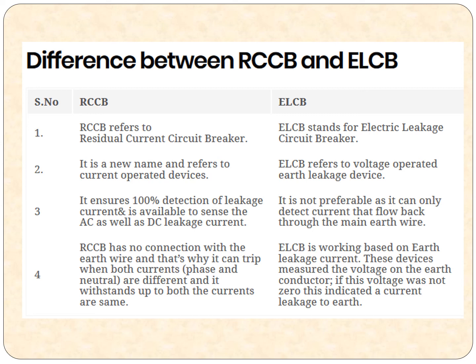That means you are supplying some current, it is energizing the load, and it comes back through the neutral. So the phase current has to be equal to the neutral current. But if you are having a shock, or an overload happens, your phase current and the return current will not be equal. It will be somewhat higher. That is the way it detects and makes protective action, which is 100% efficient. So ELCB works based on the earth leakage. These devices measure the voltage on the earth conductor only, so it purely depends on the quality of the earth conductor. If the earth voltage is not zero, it indicates a current leakage.